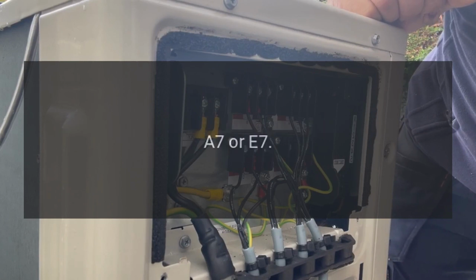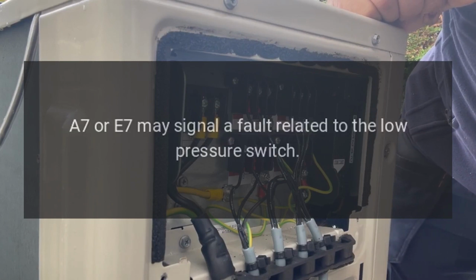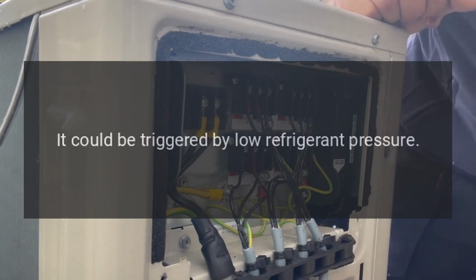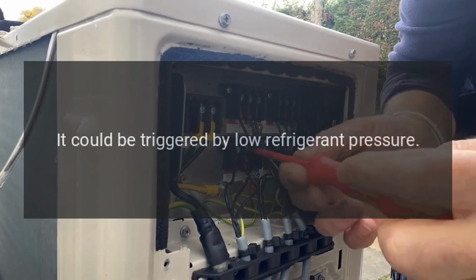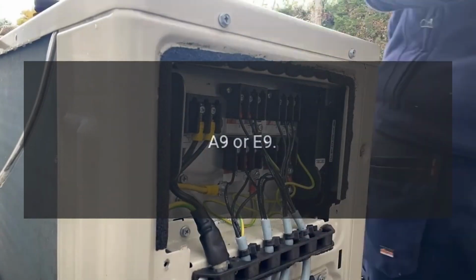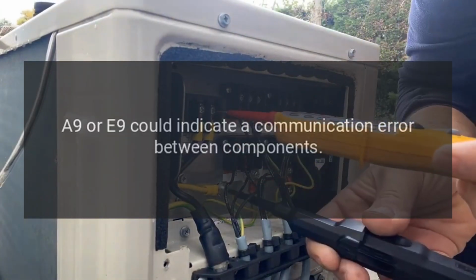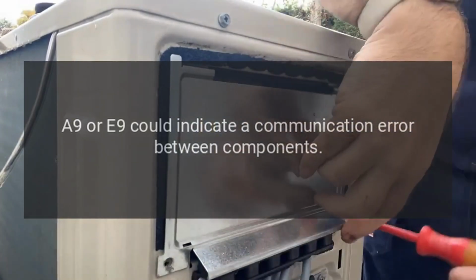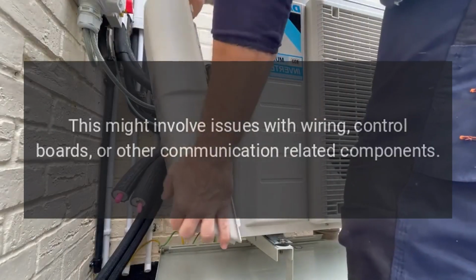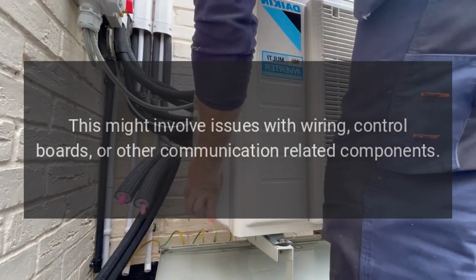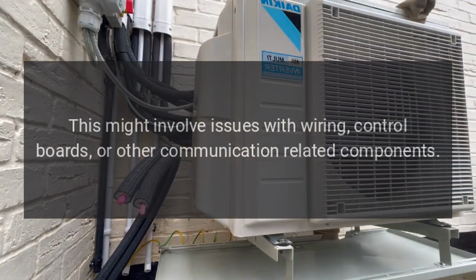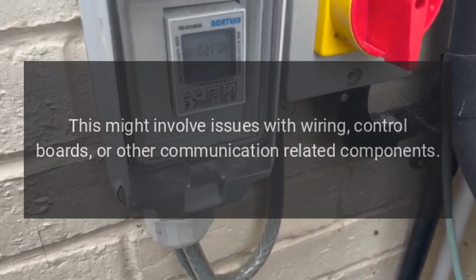A7 or E7. A7 or E7 signal a fault related to the low-pressure switch. It could be triggered by low refrigerant pressure. A9 or E9. A9 or E9 could indicate a communication error between components. This might involve issues with wiring, control boards, or other communication-related components.